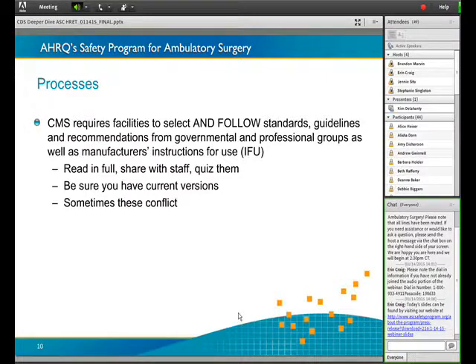Some instruments are very difficult to impossible to clean successfully, such as arthroscopic shavers. These have caused outbreaks and have been seen in the literature to do that. So investigation revealed much debris even when the IFUs were followed. So you have to look at the actual device itself, and the less crevices, the less moving parts, the less ridges, the safer the piece of equipment.